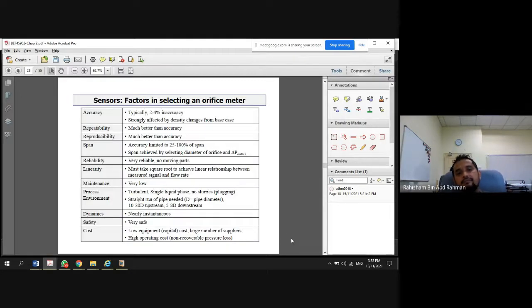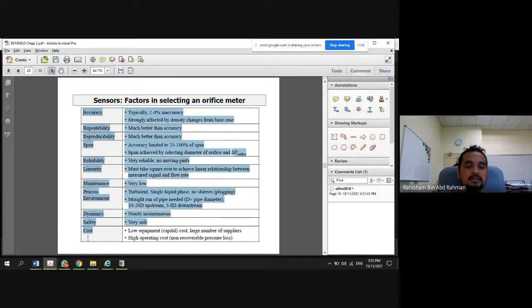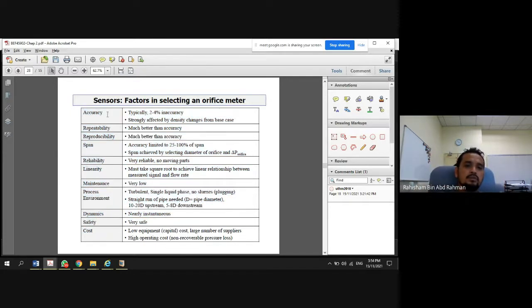All right, factors in selecting an orifice plate. These are some common factors that engineers normally consider for any sensors, not only orifice but many sensors. We consider the accuracy, repeatability, reproducibility, span, and reliability. So when talking about the orifice meter as a sensor, or any device as a sensor, we try to take all of this into consideration.